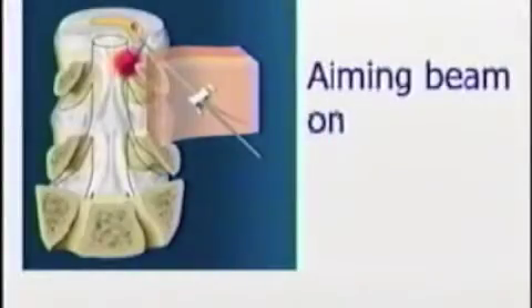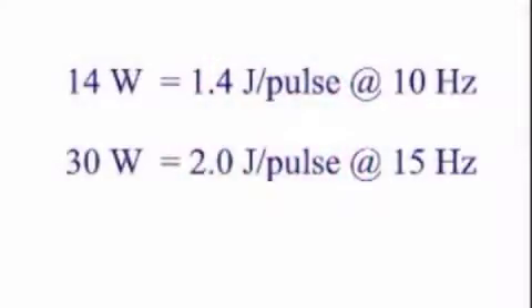Turn on the red aiming beam. It makes the laser fiber much more visible. Set the laser energy. Many physicians start at 1.4 joules per pulse at 10 pulses per second, or 14 watts. Later in the case, after you have established a cavity, you might increase the pulse energy to 2 joules per pulse at 15 pulses per second, or 30 watts. You need to choose an energy that works safely for the individual patient.